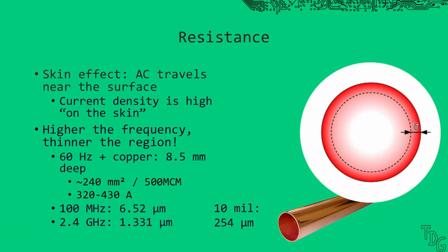One thing you should keep in mind in special cases, DC and AC resistance can be different. If you go AC, the moving electrons tend to concentrate on the outside of the conductor. Current density becomes significantly less in the inside with higher frequencies. A copper tube can have the same resistance as a solid rod at high frequencies. This effect is almost negligible with line voltages 50 or 60 hertz, and a few hundred amps are a lot. But if you go radio frequency, even the thin as regular signal trace can become oversized.